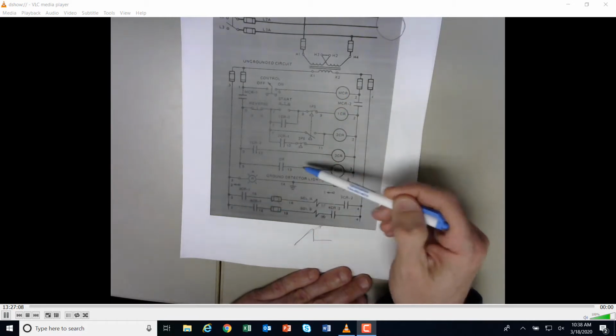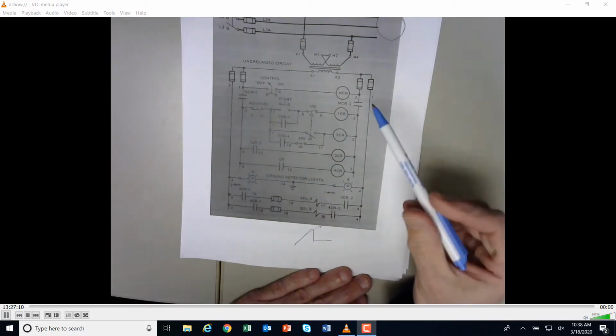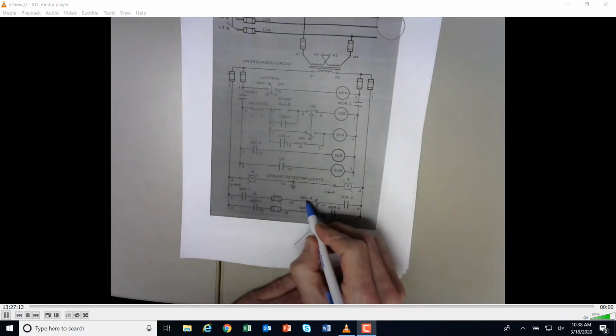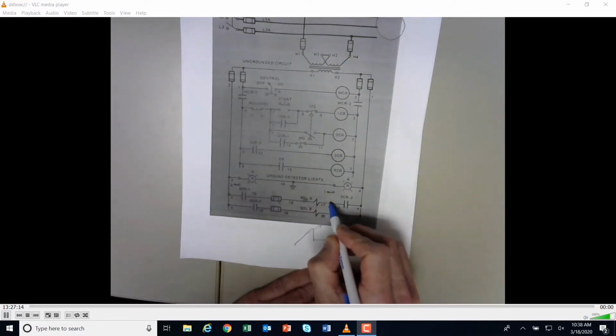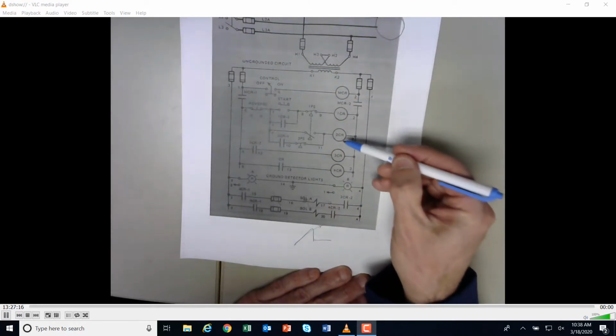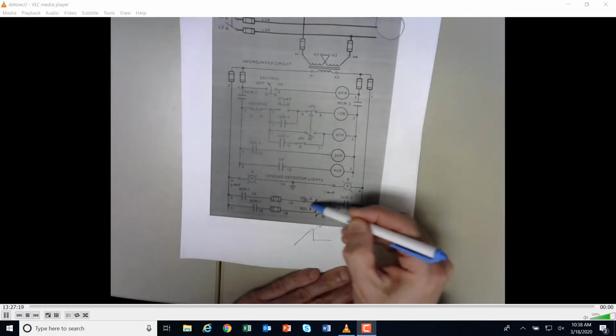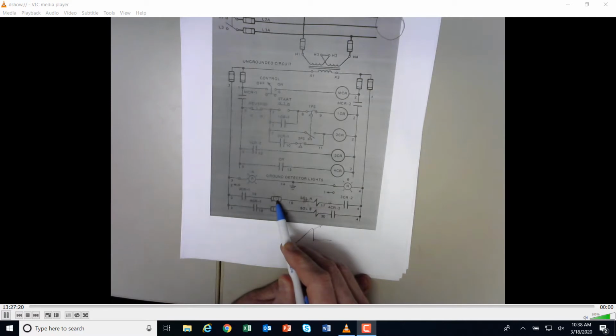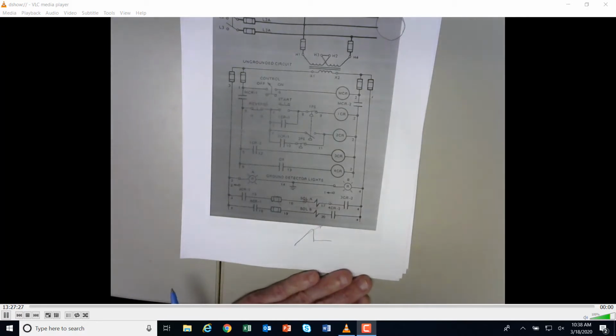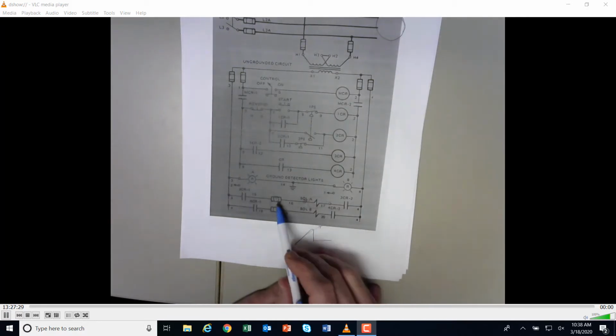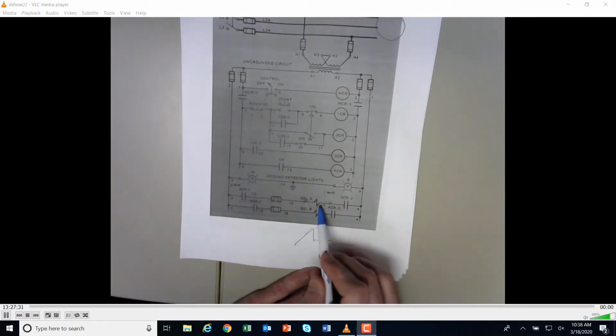We can put our multimeters on, a Fluke, and find out where voltage is. Like I said, we would start, first of all, by checking on each side of the load. So if you start going here, this is good load, good, good, good, good, good, oh, bad, then you can move right to this fuse right here, and you would find that it's shot, but the entire process kept running. So that's why these fuses are here, just to isolate individual components.